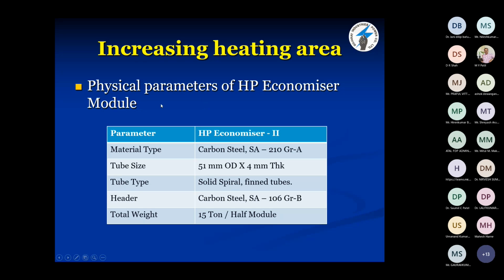Okay. Now these are the physical parameters of the HP economizer module. The module of the economizer was carbon steel SA210 grade A. Tube size is 51 mm OD into 4 mm thick. The total weight of the module was 15 ton for half module. If you consider the full module, it was 30 ton. And the height of the module is 15 meter.